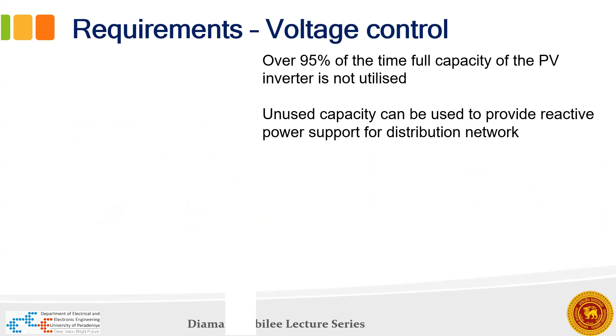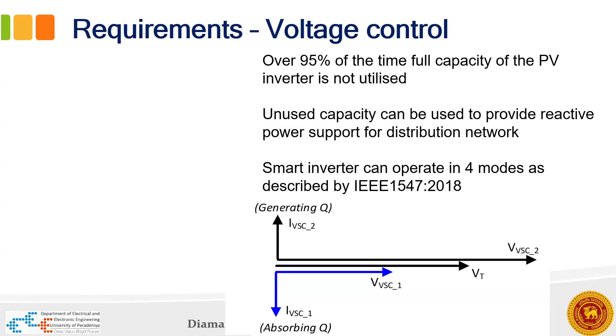So why not use it as a STATCOM, a static power compensator, where in the daytime you can absorb reactive power to bring the voltages down. At night, they have full capacity to supply reactive power to the grid to boost the voltages. This is required in some parts of the country. This is now mandatory in IEEE 1547, 2018 version.